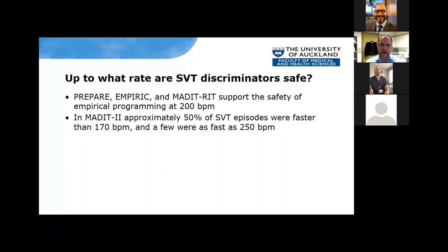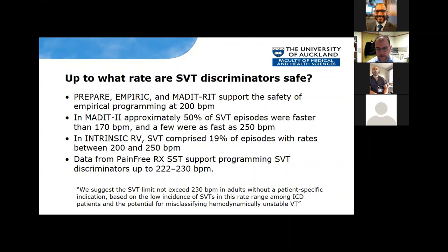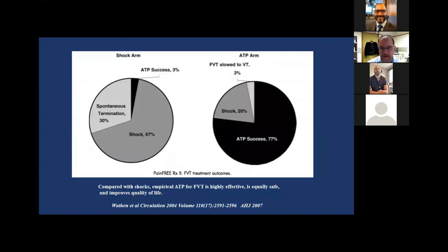Empirical programming up to 200 beats per minute is well-supported. Data from MADIT-II showed about half of SVT episodes are faster than 170, and some get up to 250 beats per minute. About 20% of episodes between 200 and 250 beats per minute are SVTs. Data from the PAIN-FREE SST trial supports programming SVT discriminators up to around 222 or even 230 beats per minute. So we suggest the SVT limit should not exceed 230 beats per minute. You're good up to 200 definitely, and probably good to 230. Beyond 230, you really need a patient-specific indication to avoid misclassifying really fast, unstable VTs.